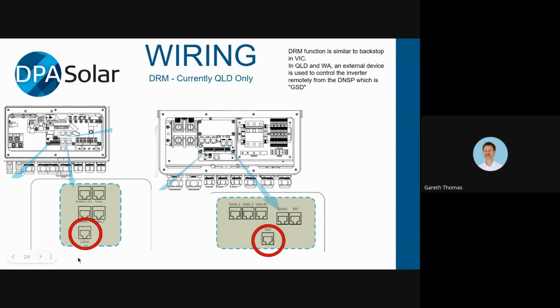There's a DRM plug. And I'll talk about this a little bit more when we're going through the commissioning software steps. But basically, you don't need to use it unless you're doing DRM in Queensland, unless you're using a GSD device. You need to have DRM switched off if you're not using it.